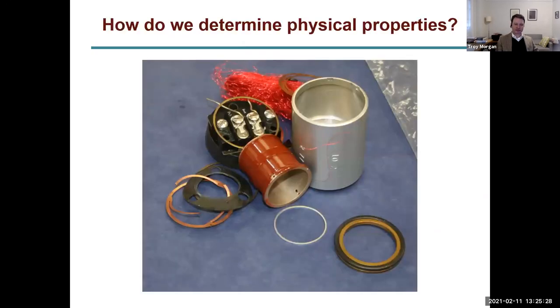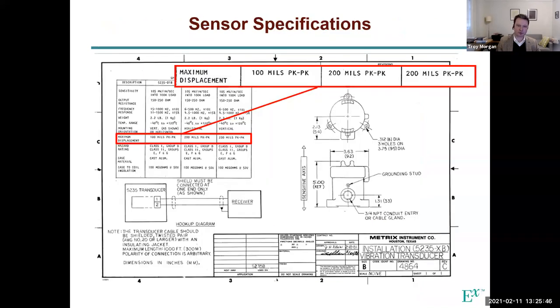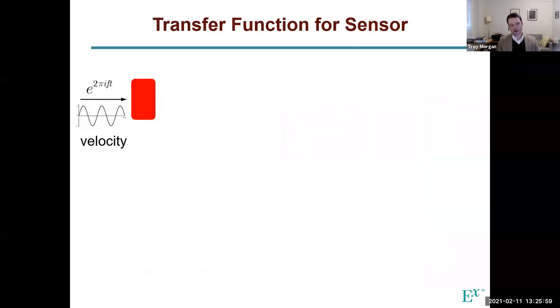All right, so we had a model of the velocity sensor. We asked the operator of the plant to send us one, and they sent us this - a dismantled and destroyed sensor, which wasn't really useful for us, because we wanted to actually test it and figure out what it did under different types of input motions. One important thing is the specs had what the peak-to-peak allowable motion was, so how much motion vertically could take place of that mass before it would impact the housing. You'll see where that comes in a moment.